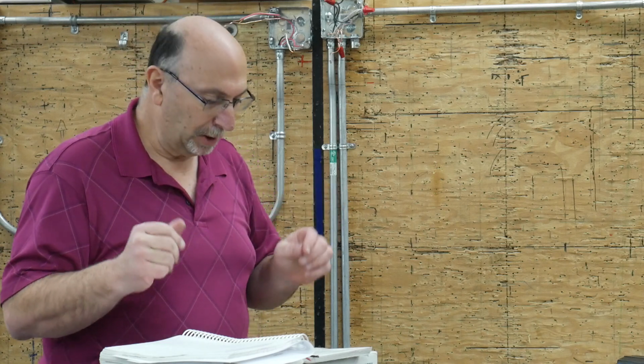Next, sub-rule 2, except as provided for in sub-rule 3 and subject to the details given in sub-rule 1, boxes of the nominal dimensions given in table 23 shall not contain more insulated conductors of a given size than permitted by the table. It's very important that you do not overload your boxes. You actually will create more damage to the conductors and create more heat. So make sure you size the box accordingly.